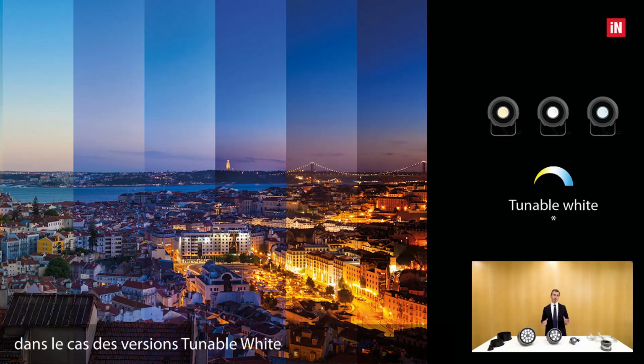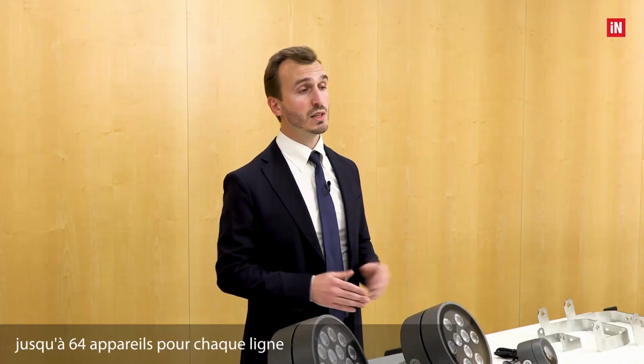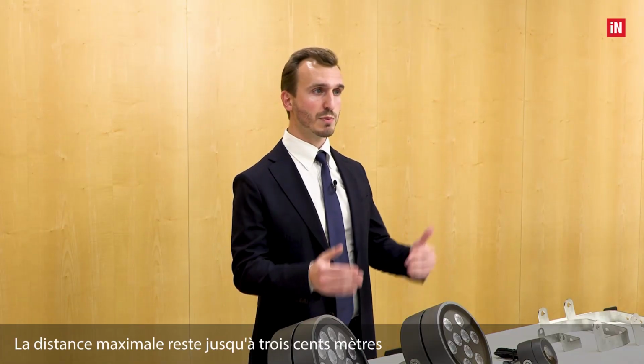Differently, in the case of the tunable white version, the addresses occupied are 2 per device. Therefore, up to 64 devices can be connected for each different line. The maximum distance remains up to 300 meters.